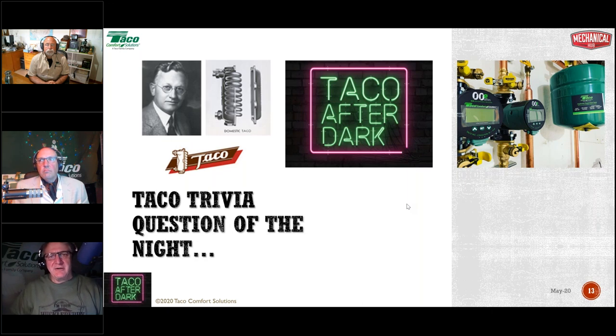Absolutely. In fact, when we had our Flow Pro Designer heat loss software, we had engineers tell us that they would not use it for heat loss unless there was a user adjustable safety factor. What's another word for user adjustable safety factor, Dave and Rick? Fudge, baby, fudge. Yeah, CYA. If I'm going to do whatever this thing comes up with, I'm adding 20%, because I don't want the phone call. It's just the way it goes. It's not that they're far off, it's just that that's kind of where it is. I'm the king of load fudge, right? There you go, Jim.